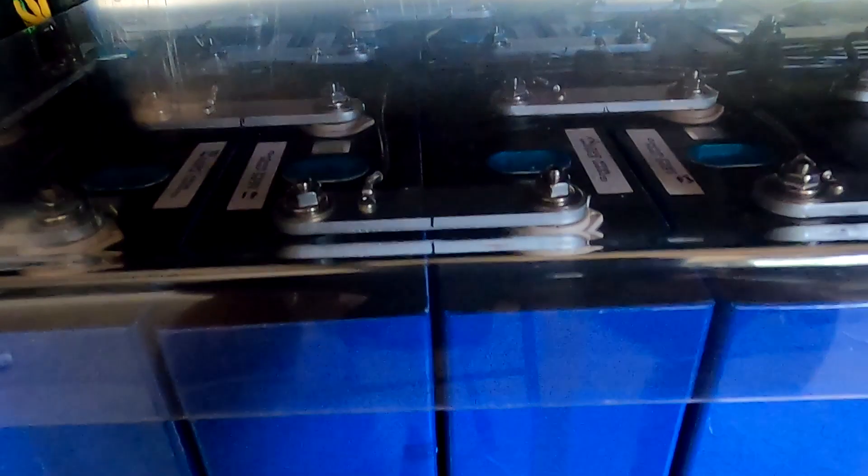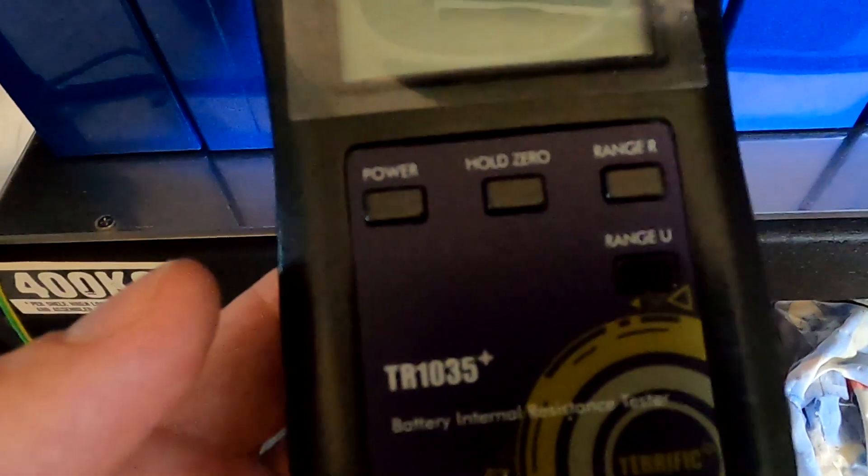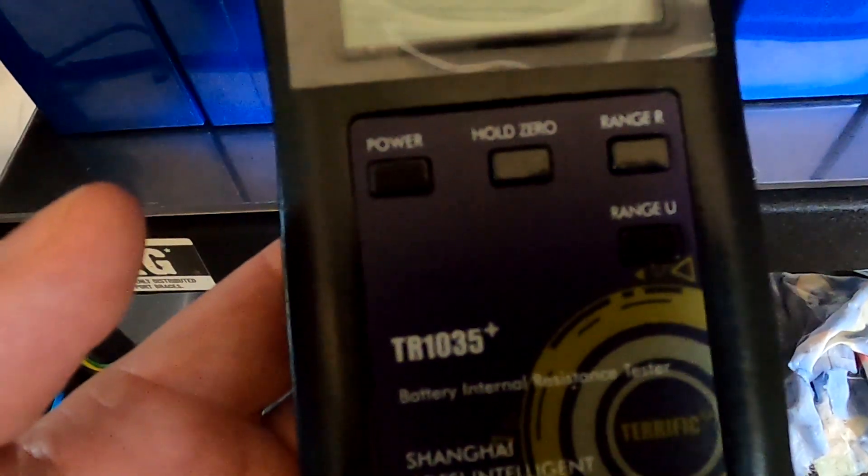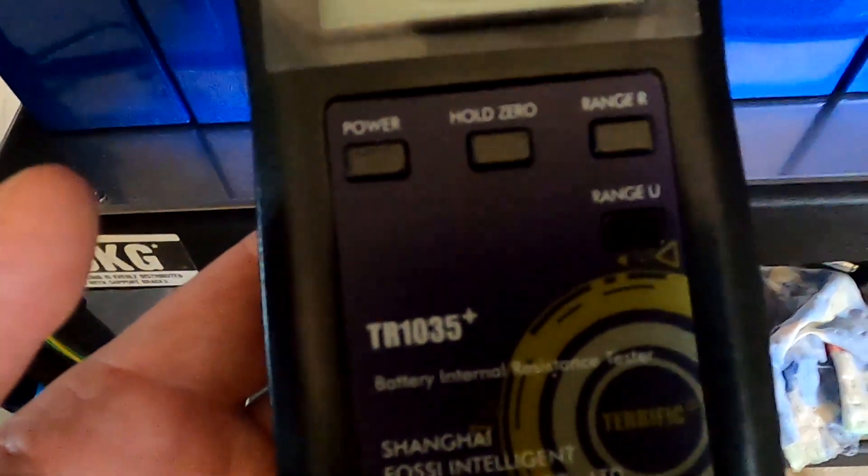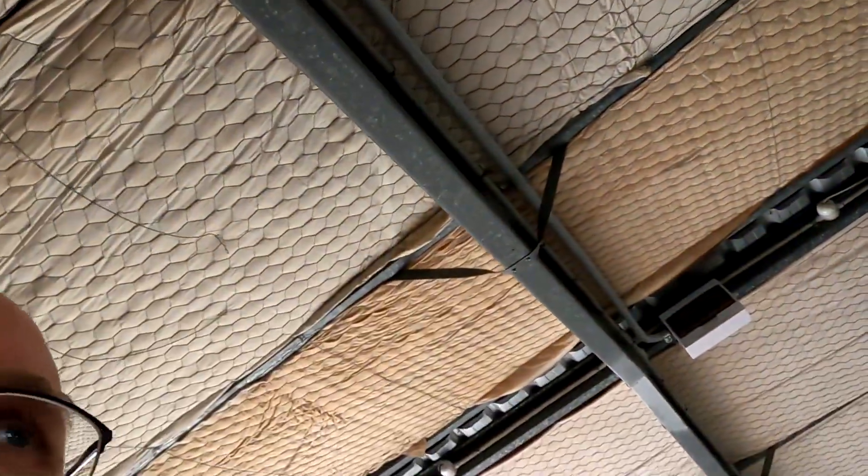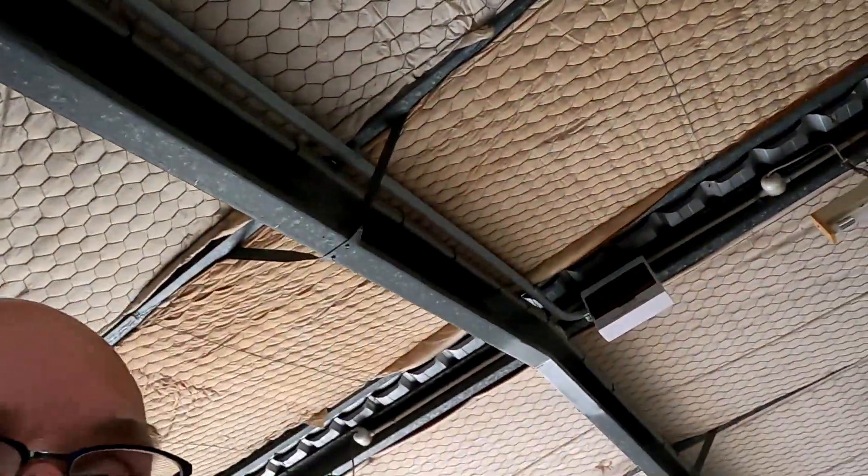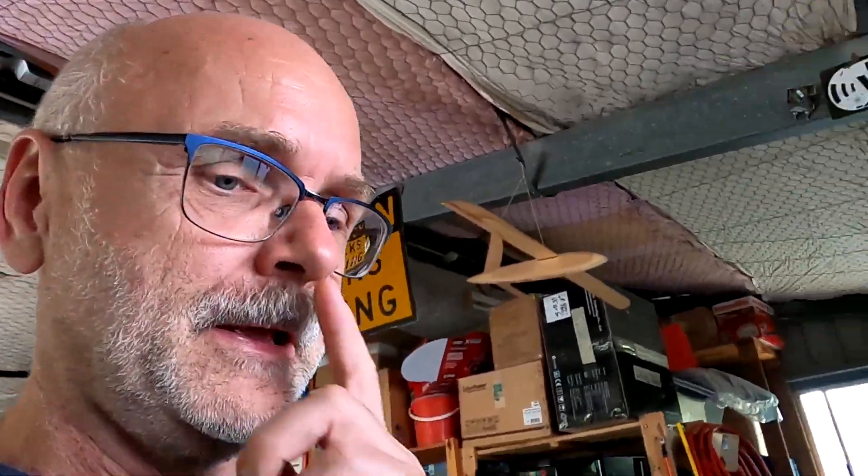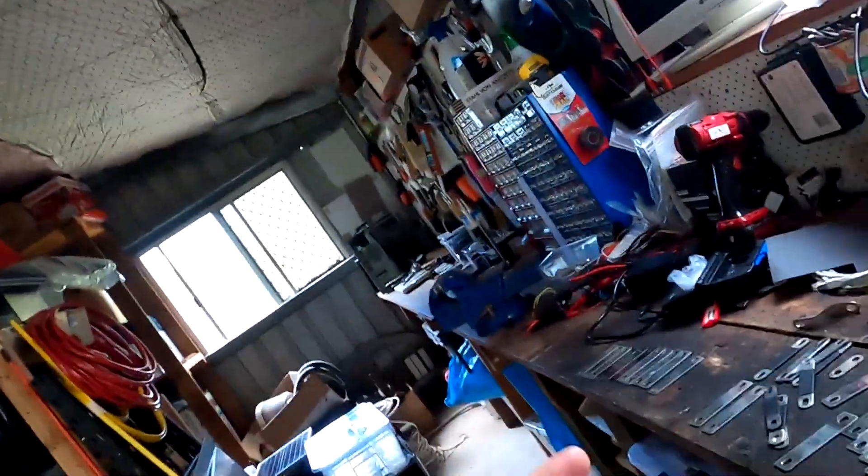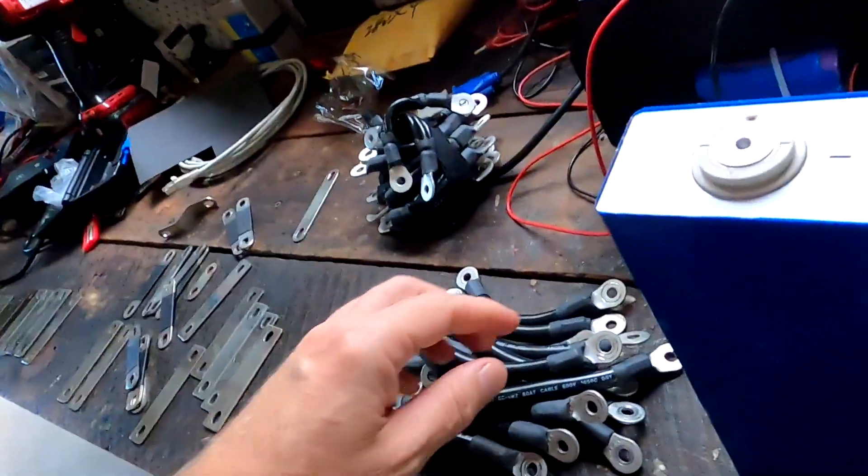Well guys, I have also tried to measure the resistance here of the bus bars when we had the problem, and I couldn't see any problems across the whole range of terminals and bus bars here with this device at all. All the resistances I could measure were in the same area, so there was not much difference at all.